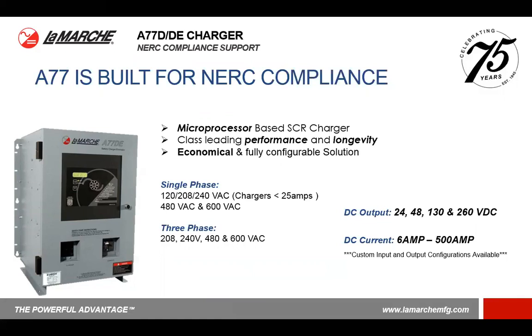It was originally built to comply with the NEMA PE5 standard, and then later on, as new standards have been in development alongside NEMA PE5, such as IEEE P2405, the A77DE does comply with the industrial battery chargers. This charger was built to work in multiple and different installations. So for that reason, we've made it with the flexibility to configure the charger with different AC voltages for the input and different DC voltages for the output. The outputs are offered to operate in a 24-volt DC system, 48-volt, 130, and also in 260-volt DC systems. The charger is offered in either single-phase or three-phase inputs.